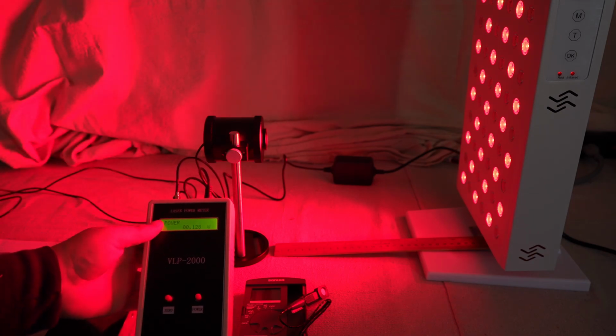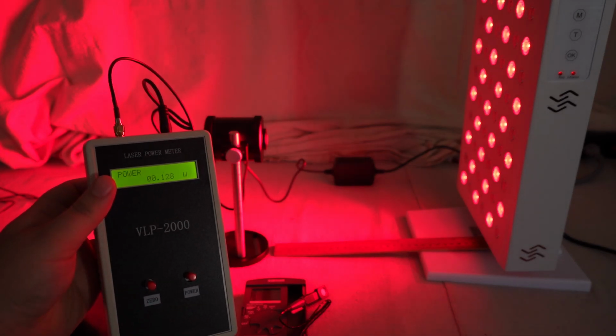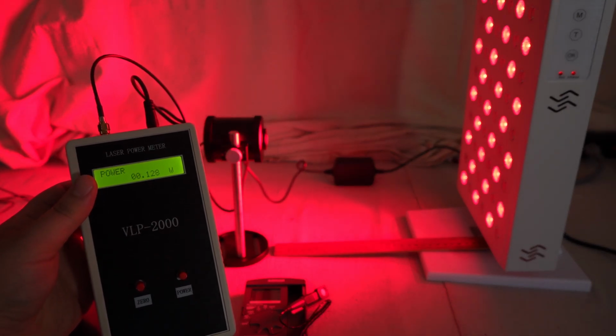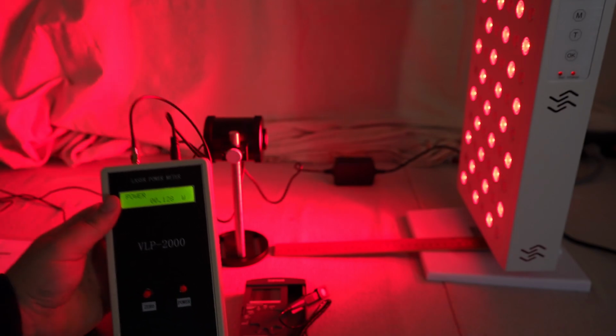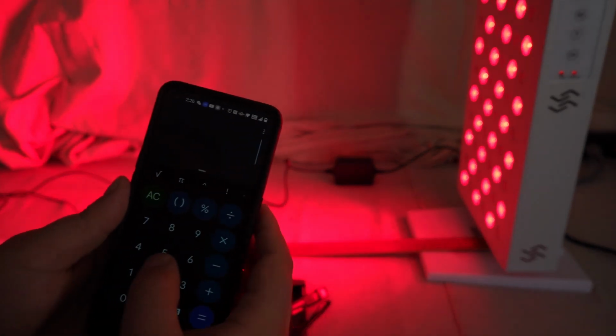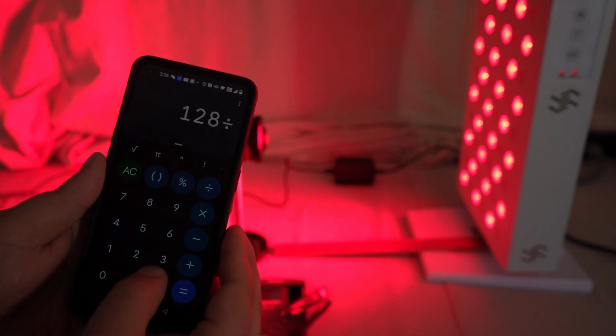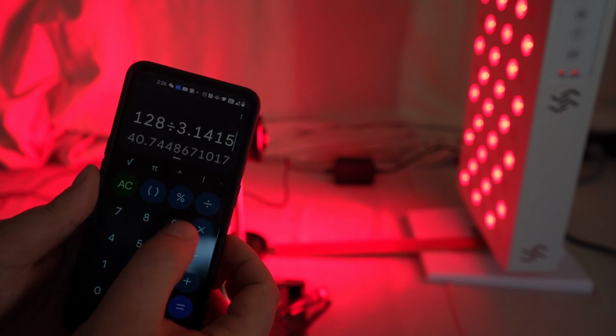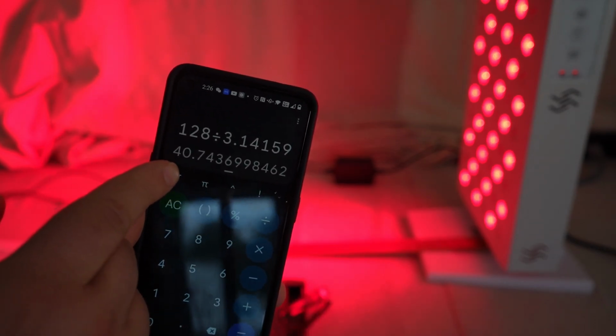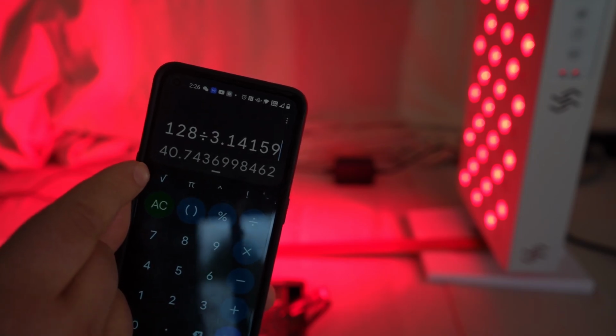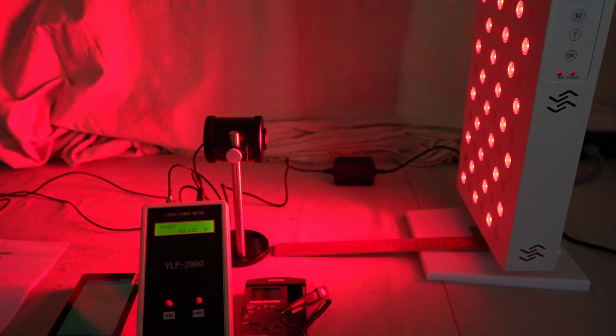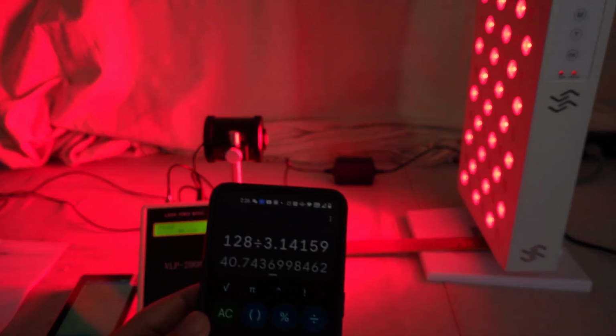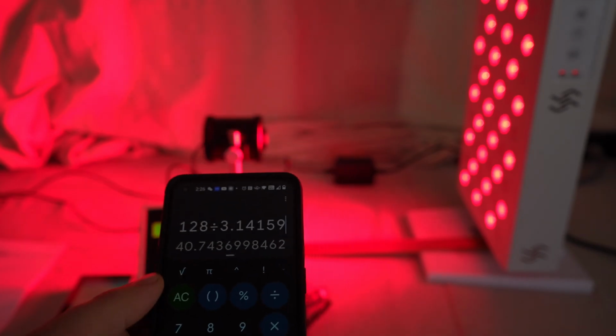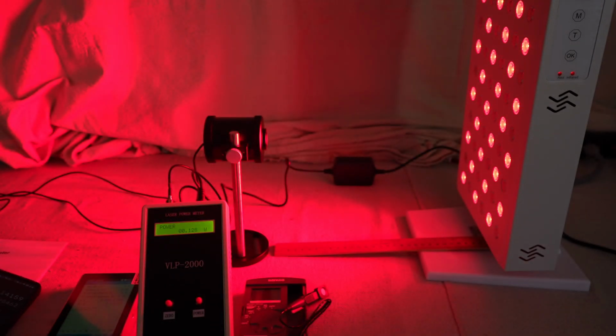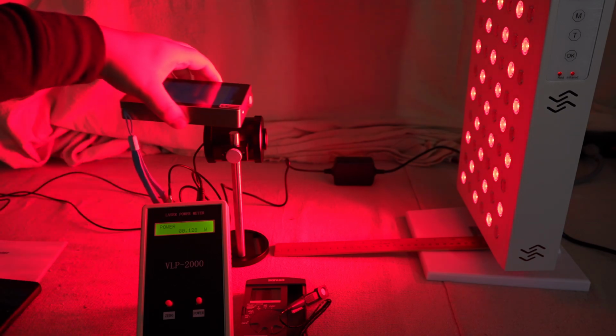So it looks like we've stabilized. We've got 128 milliwatts. So again, it's just a simple conversion from watts to milliwatts, so it's 128. And so the calculation is really easy. So 128 divided by 3.14159, and we get 40.7, so almost 41 milliwatts per centimeter squared. So again, that's about 12 inches away. We got the ruler out there. And so it's about 41. So that's the number we need to remember, and we're going to cross-check it with some of our other measurement tools.